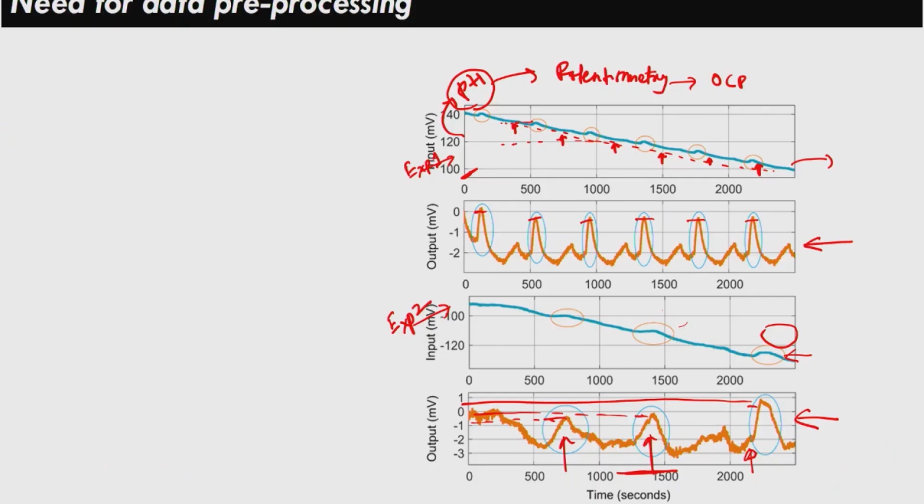If you think of one of the challenges, the first feature that is present in wearable sensors like we see here is drift, sensor drift. There is always some sort of a sensor drift. This sensor drift can be linear or it can be non-linear. What we see here are examples of mostly linear sensor drift.